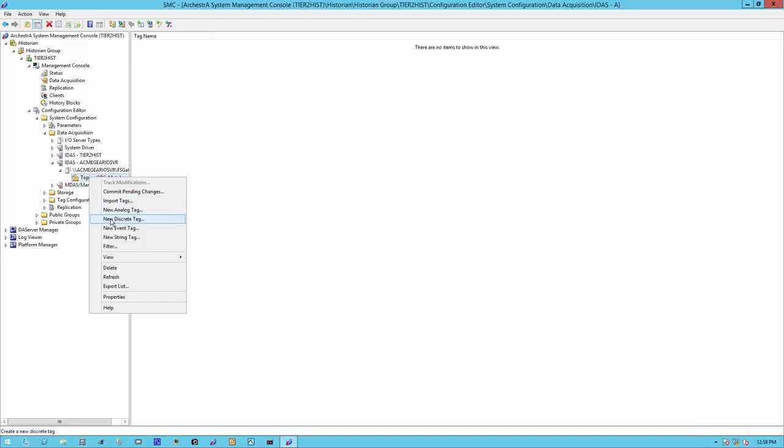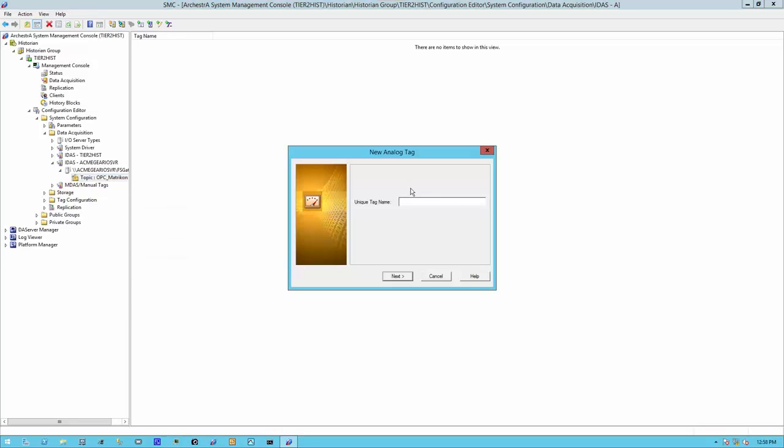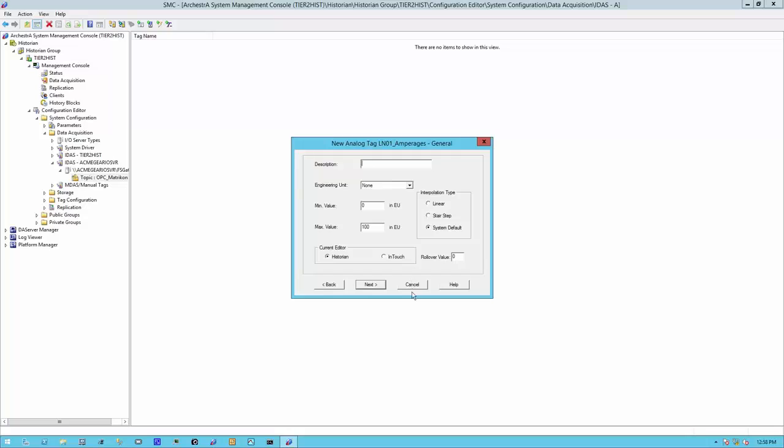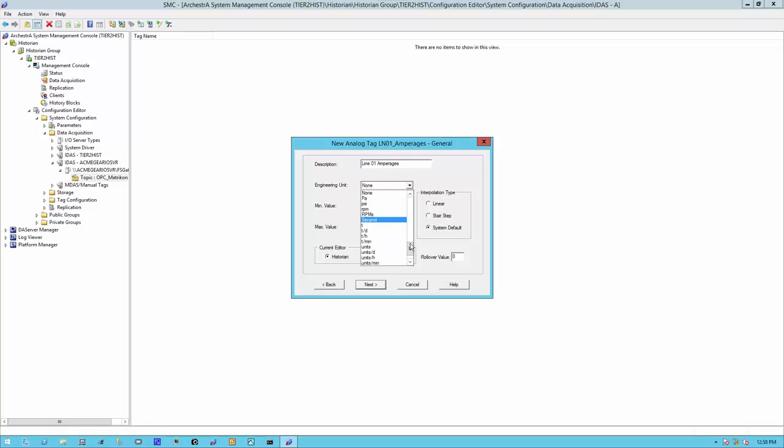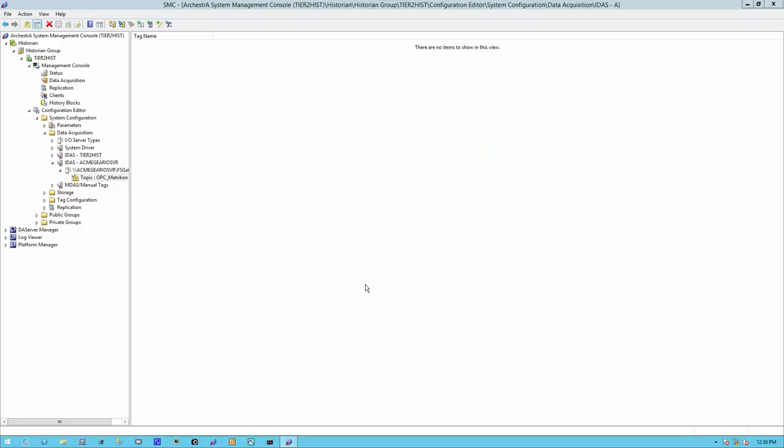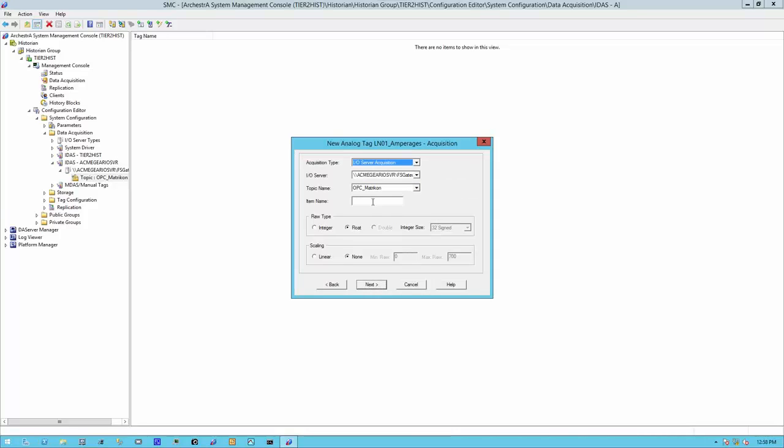Now let's create a new analog tag. I'm going to call it line 01 amperages. Click on next. I'm going to configure it. Set my engineering units. I'm going to select what I expect here as far as amps. Click on next. Now, this is very important. We have to determine exactly the item, the exact item that we want to put here. So let's head back to our IO server and make sure we got it right.